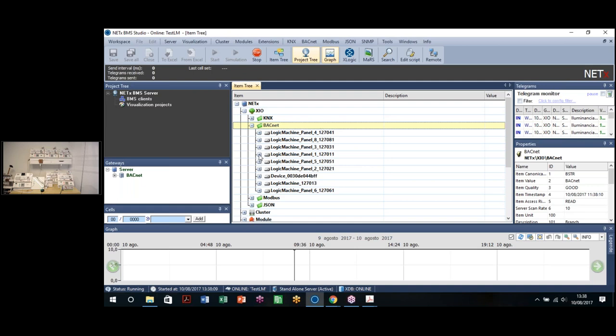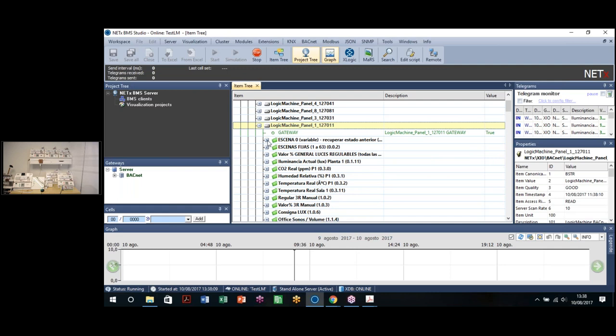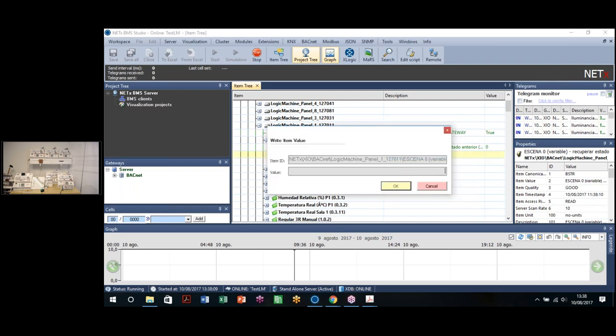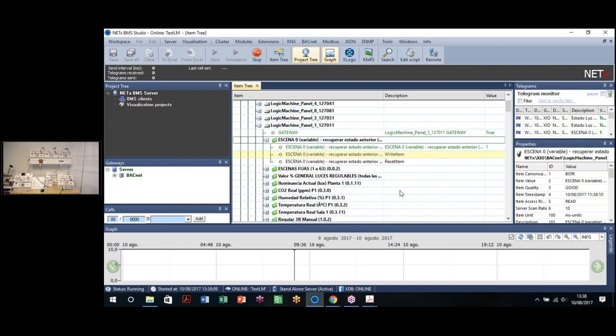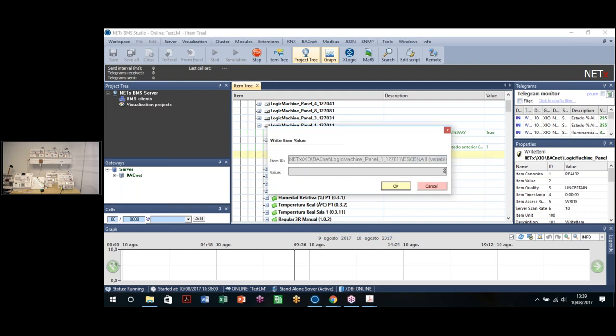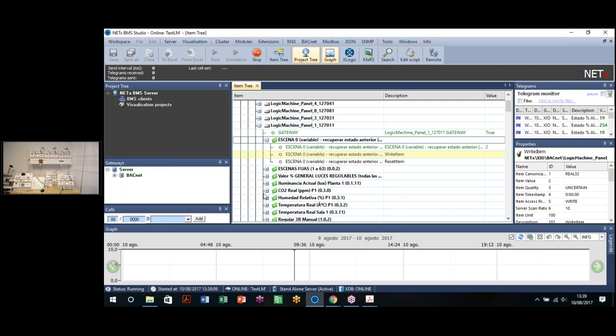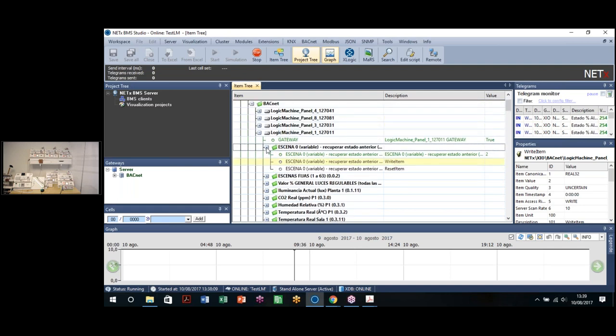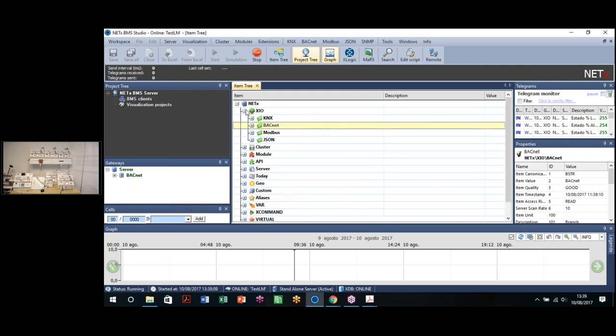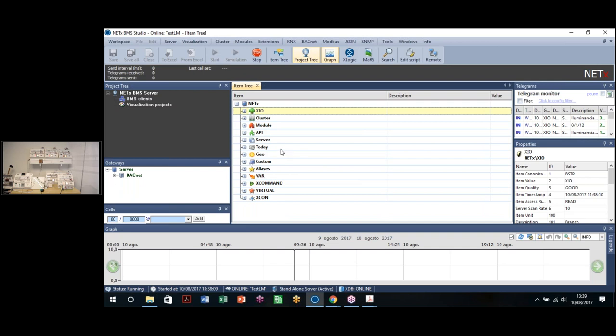So for example, if you want to take one panel, you have here the objects, and since this is a BACnet object, we can test writing, just to test that we can send some information, and you can see the result in the camera. So let's change the scene to another one, and it's changing. So you have all your objects as a BACnet object. It's very interesting because if you have a BACnet SCADA, a BACnet client, you can also integrate many things here, including for the BMS for a hotel, for example, the Fidelio software or the door access using interfaces like Kaba or Vingcard, Salto, or all these kinds of devices.